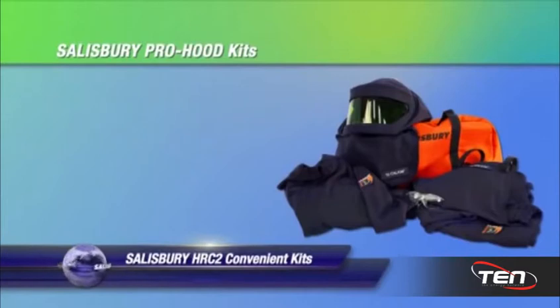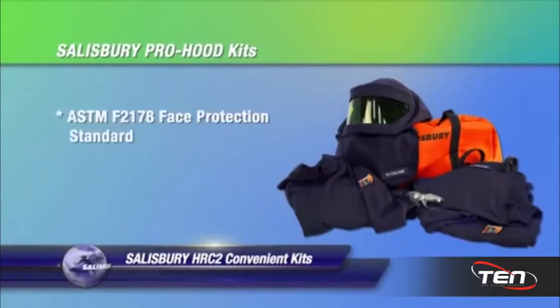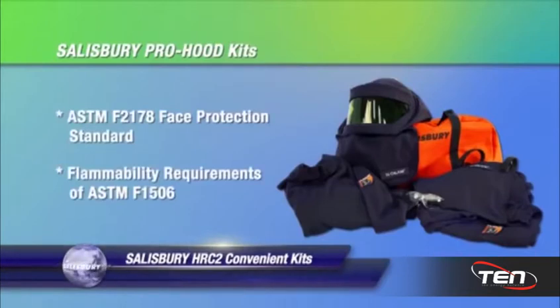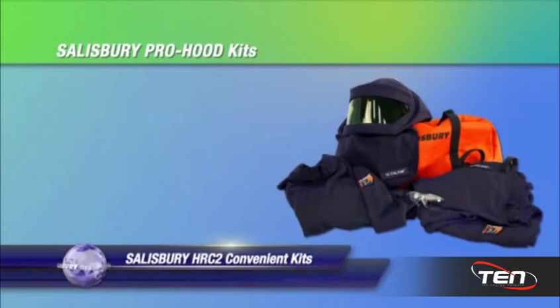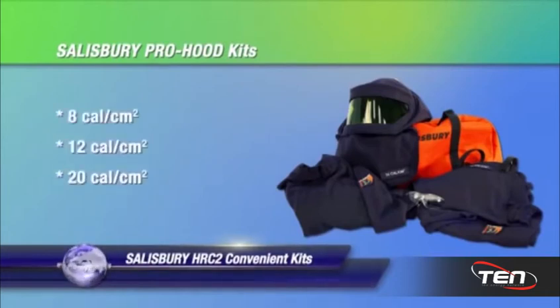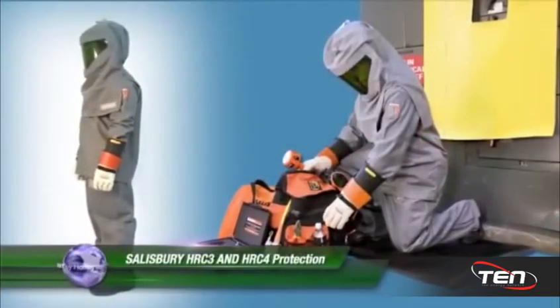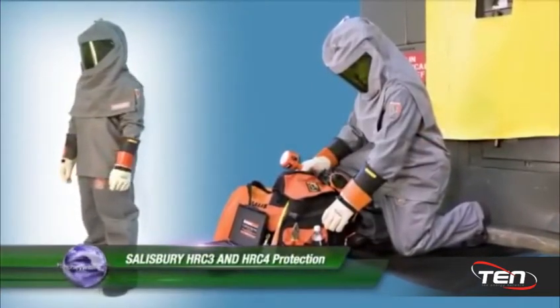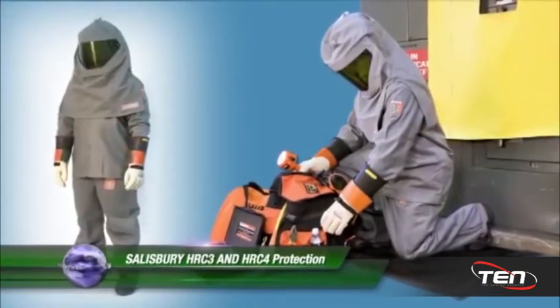The Pro hood meets the ASTM F2178 face protection standard and the flammability requirements of the ASTM F1506 standard. The Hazard Risk Category 2 kits are available in 8, 12, and 20 cal per centimeter squared in numerous sizes. Now let's look at the necessary clothing to meet the Hazard Risk Category 3 and 4 requirements.